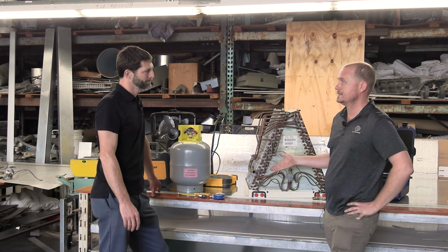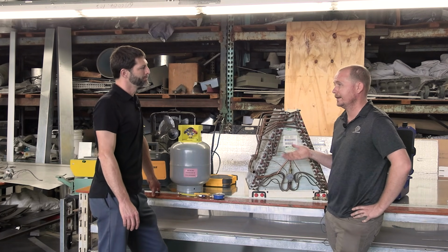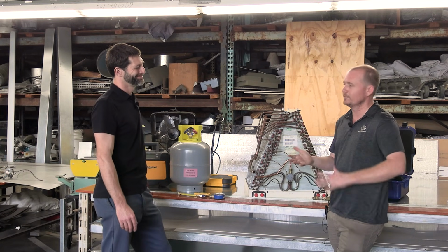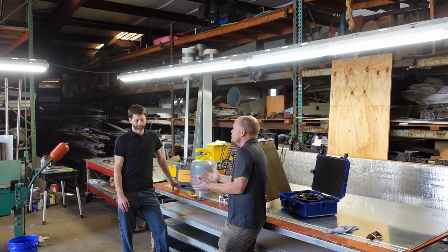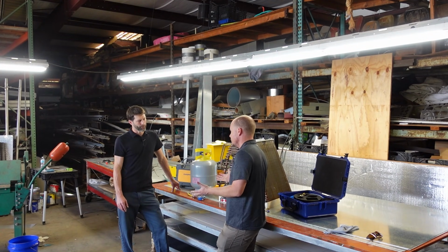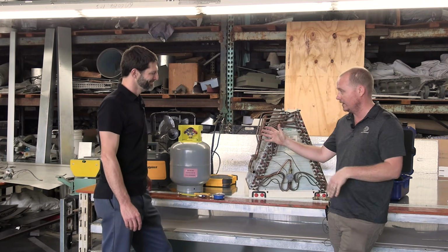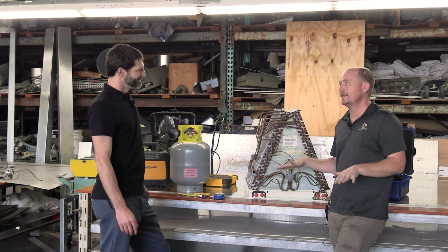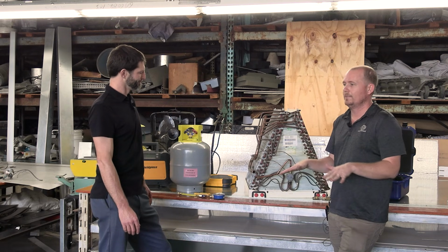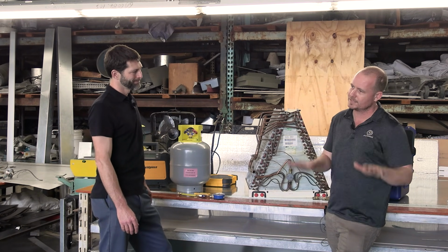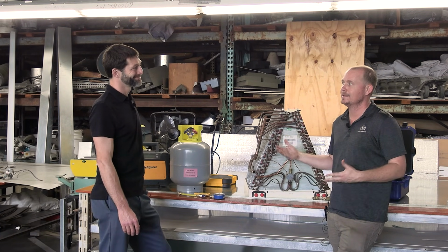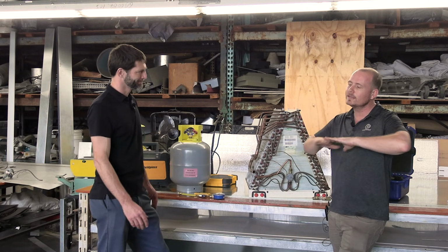When you talk about EPA standards, most of what we work on, and again, I'm making a big assumption here because some of you may work on low pressure refrigerants, but most of what we work on are high pressure refrigerants in air conditioning. So that's a quick caveat. But really, we generally just need to get the system to atmospheric. That's also advantageous because when you pull a system below atmospheric, if there's any leaks in the system, you're going to pull air in. So we really want to get it to 0.